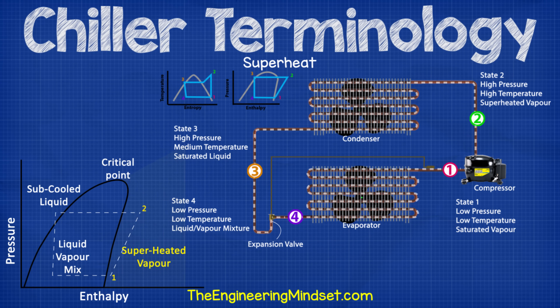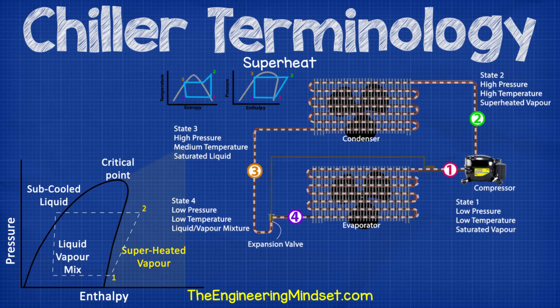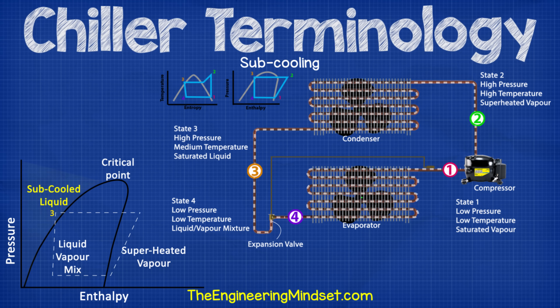Superheat. This refers to the number of degrees Kelvin that the refrigerant is above the boiling point at a particular pressure. A reading of 4 to 8 degrees Kelvin is typical. If the reading is higher, the evaporator is not operating efficiently, and if it is low or zero, there is a fault and it's possible that liquid refrigerant can reach the compressor, which will cause severe damage. Subcooling. This refers to a refrigerant which has been condensed and is at a temperature lower than its boiling point, so it is therefore in a liquid state. It is the difference between the refrigerant's saturation temperature and the actual temperature of the liquid refrigerant.